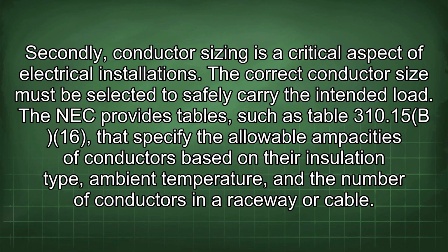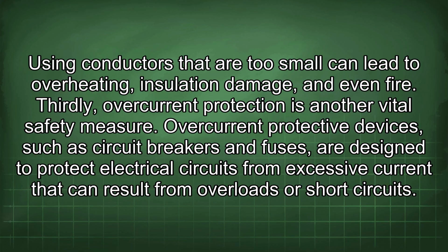Secondly, conductor sizing is a critical aspect of electrical installations. The correct conductor size must be selected to safely carry the intended load. The NEC provides tables, such as Table 310.15(B)(16), that specify the allowable ampacities of conductors based on their insulation type, ambient temperature, and the number of conductors in a raceway or cable. Using conductors that are too small can lead to overheating, insulation damage, and even fire.